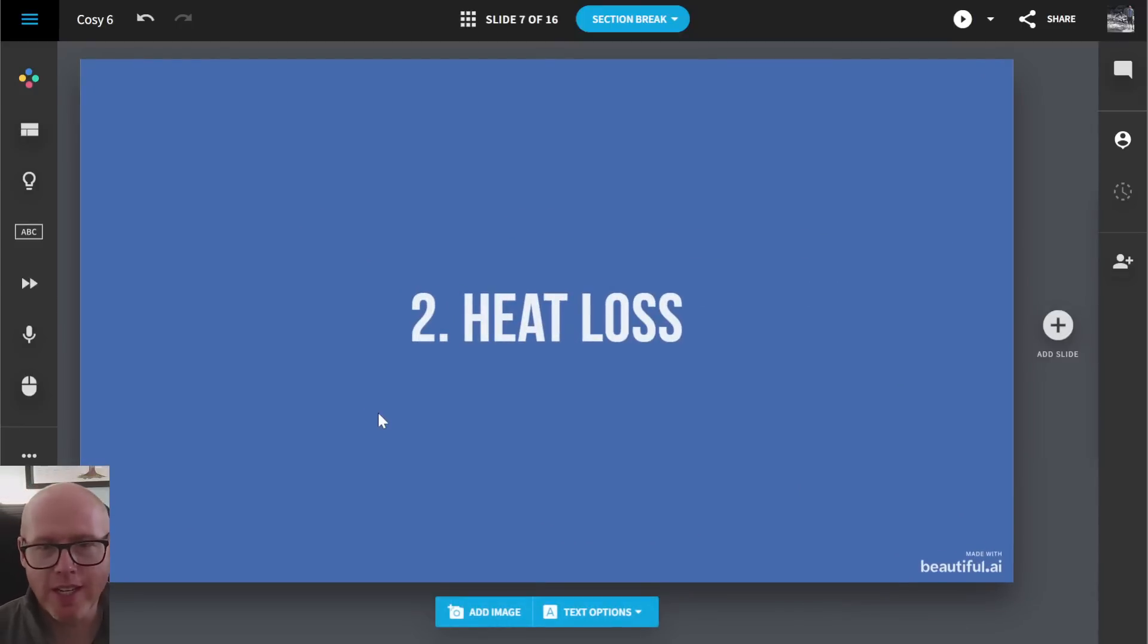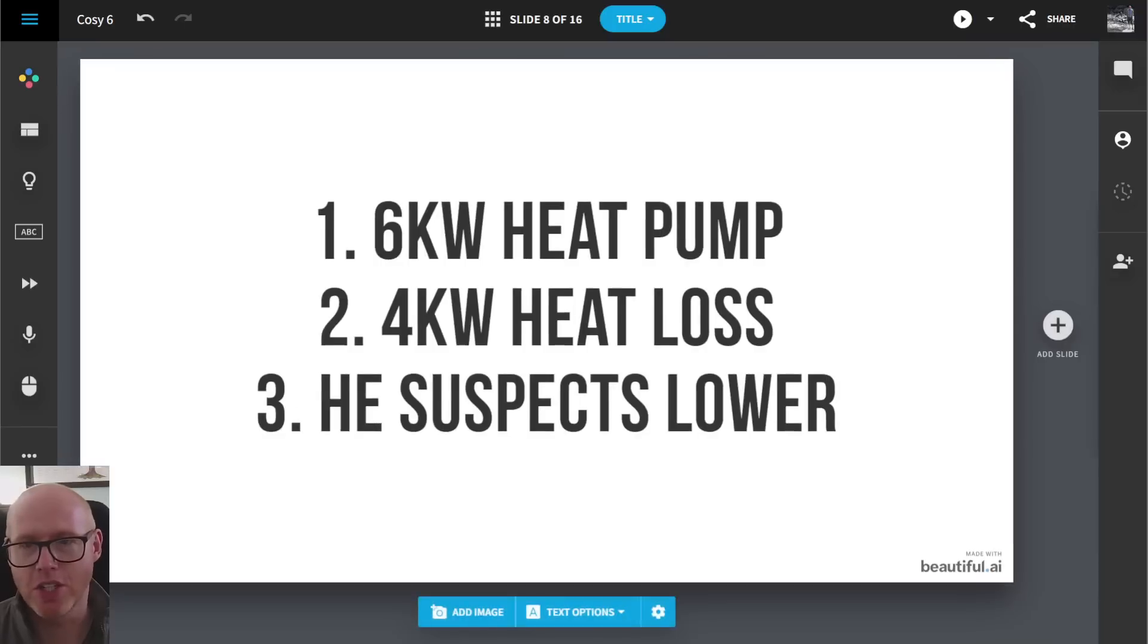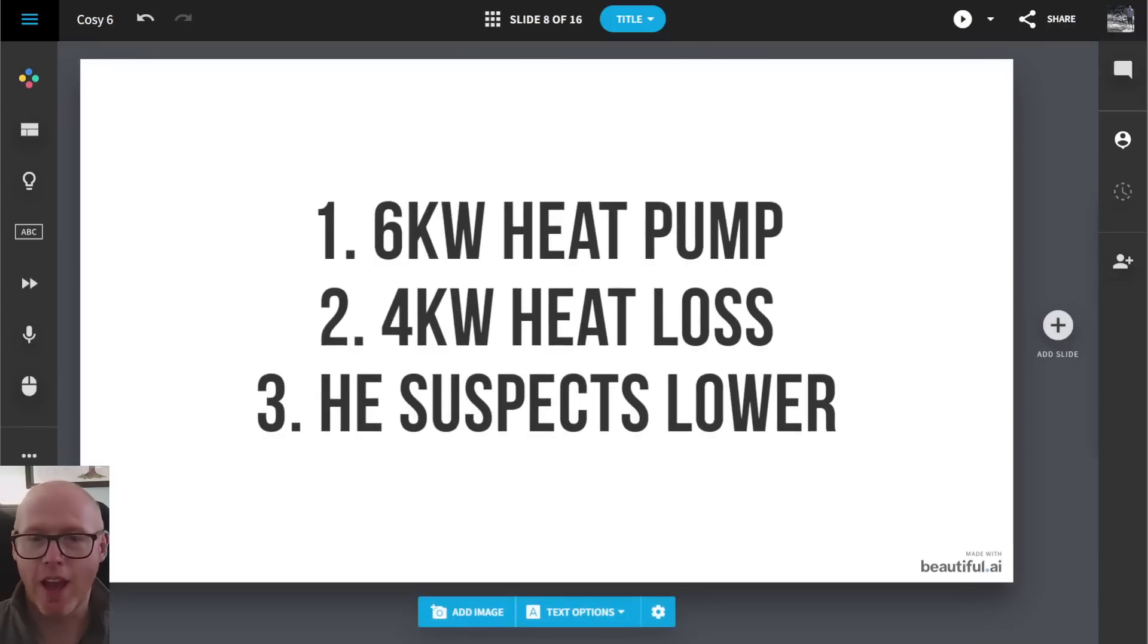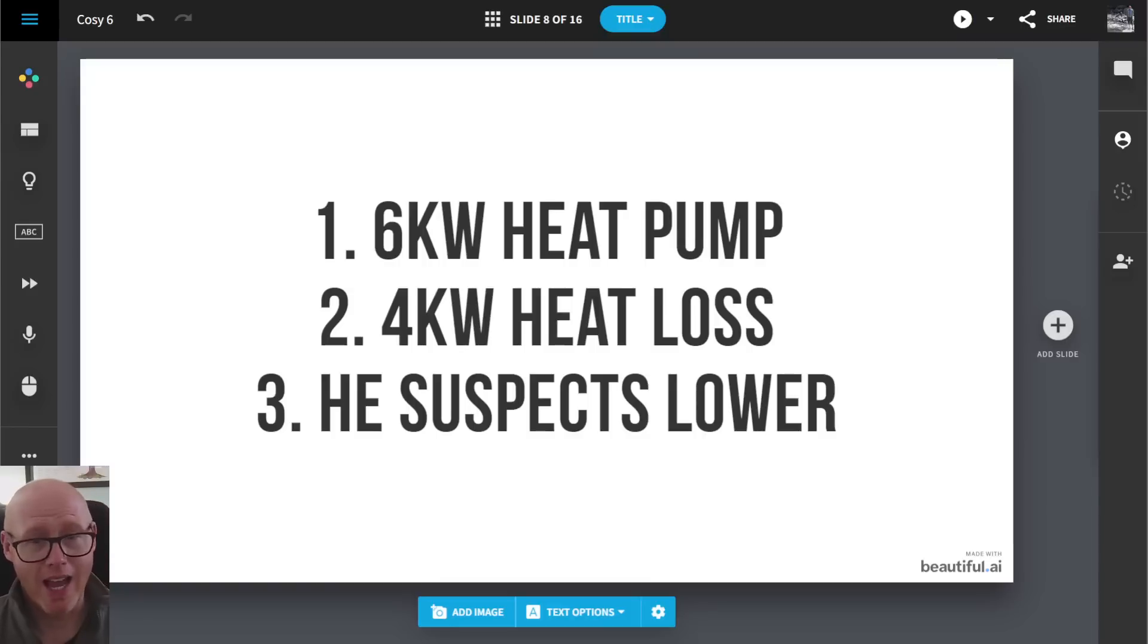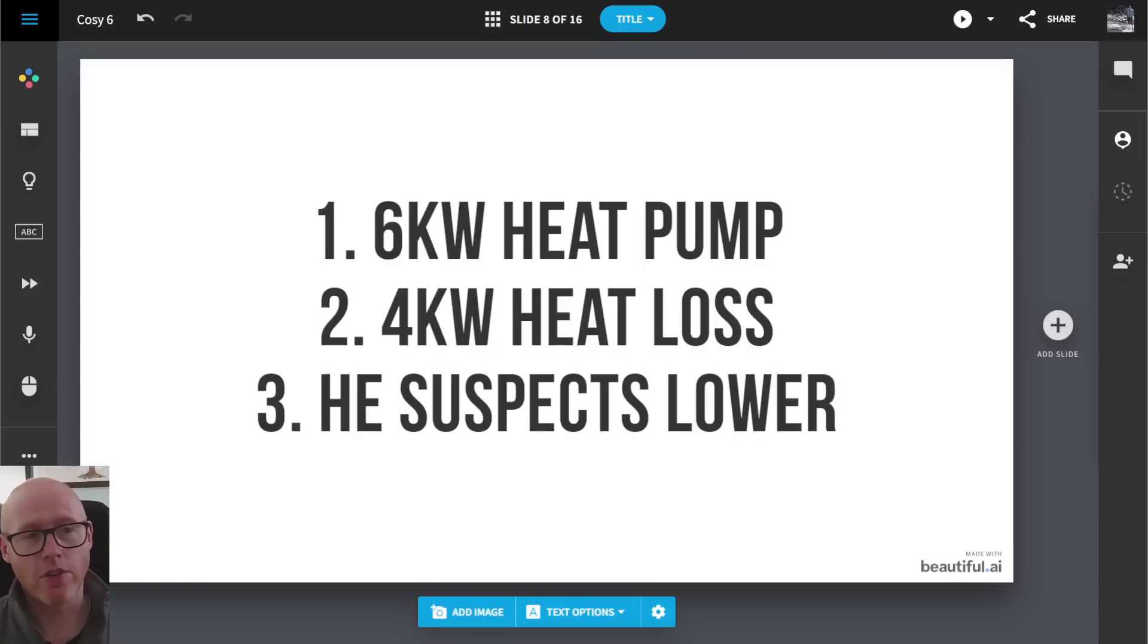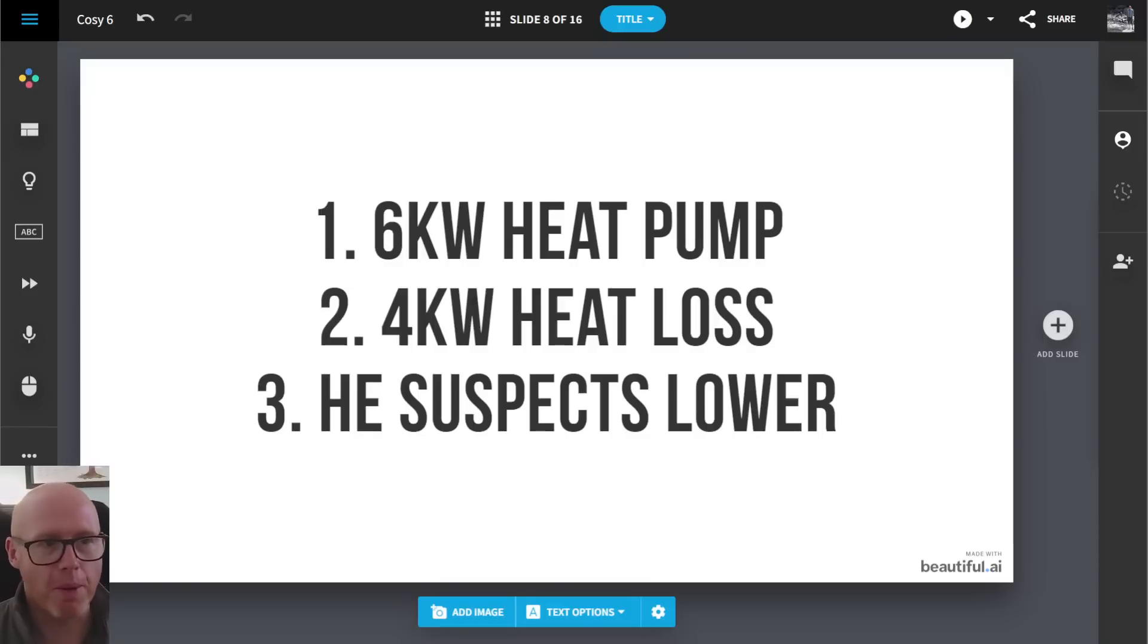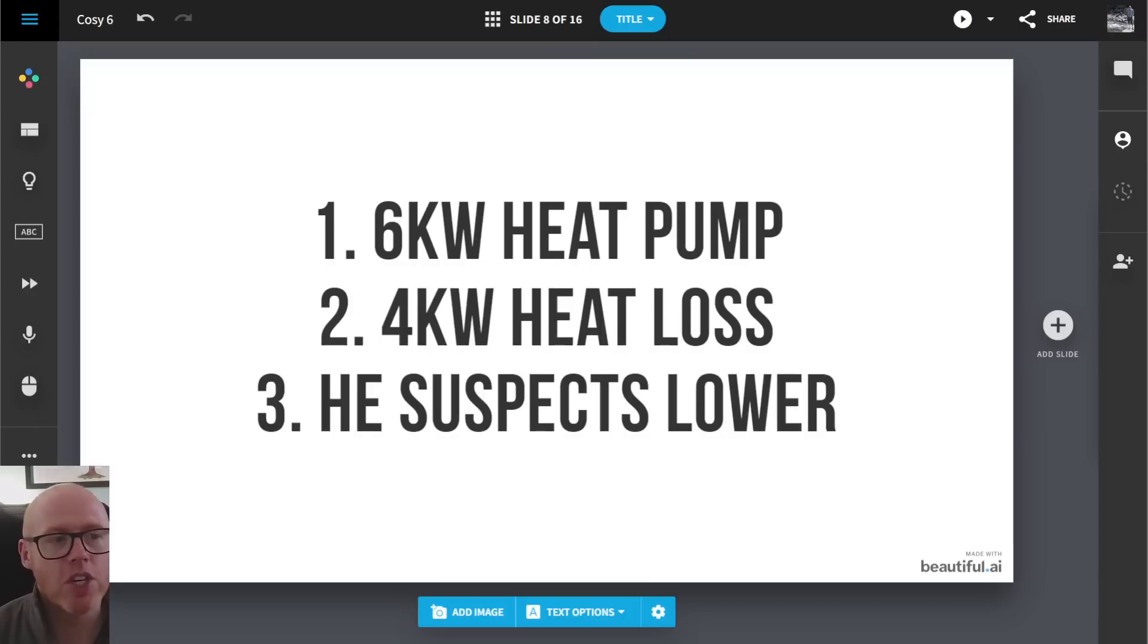So second is the heat loss. And he brings up the heat loss issue, which I've been beaten to death here. So it's a six kilowatt heat pump. He's got a four kilowatt heat loss at his design temperature. I don't know what that is. I presume where he is in the country, that's probably minus three degrees. So they're saying that it's around four kilowatts at minus three degrees that the heat pump needs to push in.